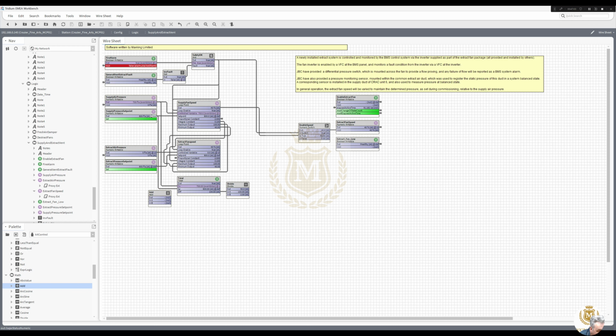So the set point is still 800 plus 50 is 850. Let's see how this works. So actions, emergency override, we're at set point 800, so at 40%. Actions, emergency override 850, we are at 100%, so it's trying its best to keep up. Actions, emergency override 860, so that's 850 plus, so that's going to be, that's wrong. So I've got to take away 50, not add 50.